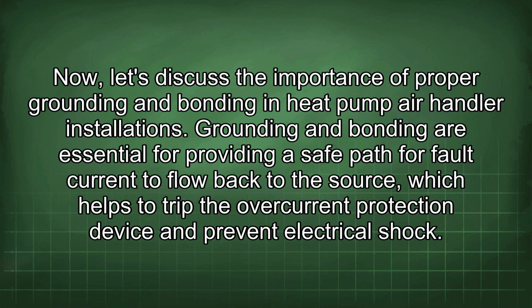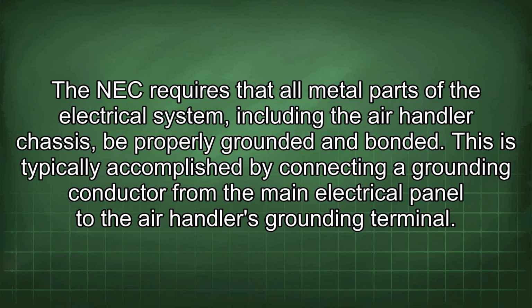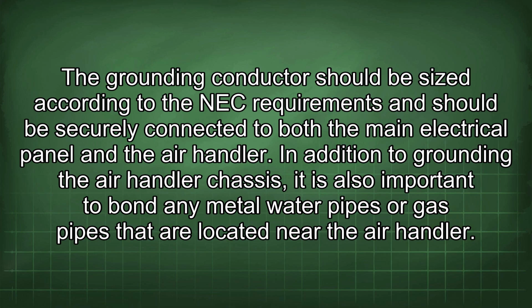Now, let's discuss the importance of proper grounding and bonding in heat pump air handler installations. Grounding and bonding are essential for providing a safe path for fault current to flow back to the source, which helps to trip the overcurrent protection device and prevent electrical shock. The NEC requires that all metal parts of the electrical system, including the air handler chassis, be properly grounded and bonded. This is typically accomplished by connecting a grounding conductor from the main electrical panel to the air handler's grounding terminal. The grounding conductor should be sized according to the NEC requirements and should be securely connected to both the main electrical panel and the air handler.